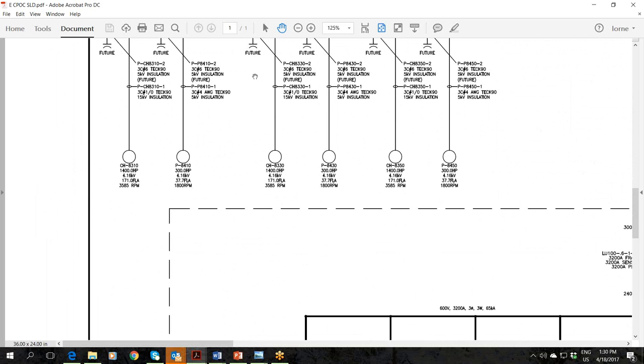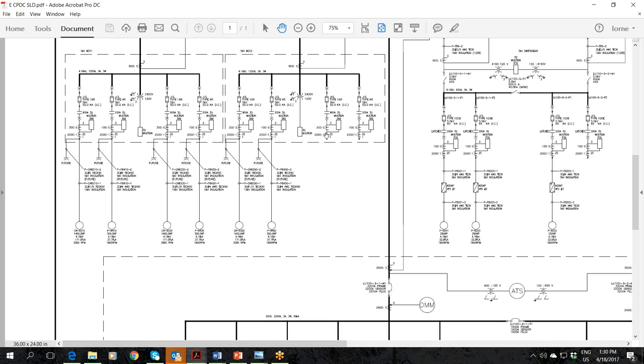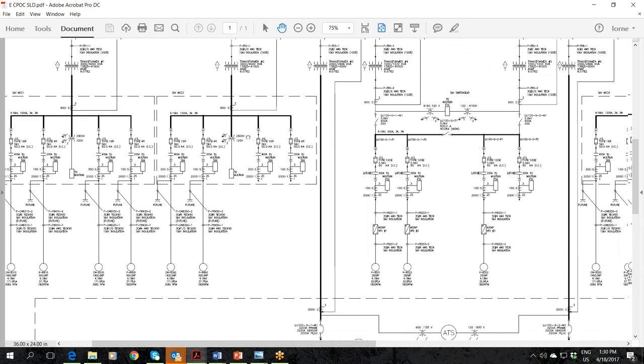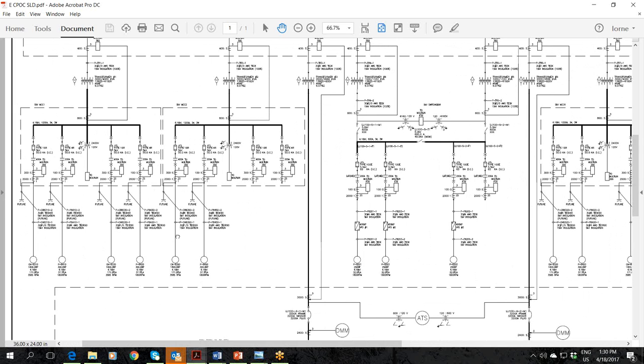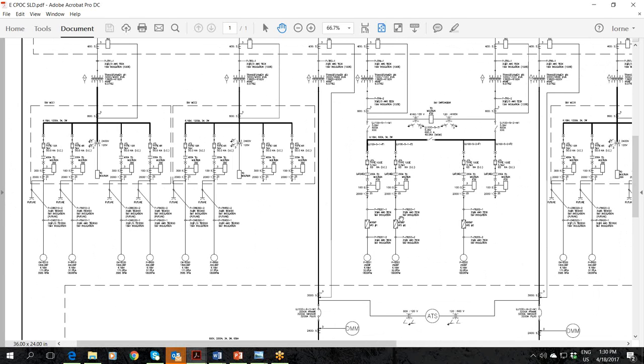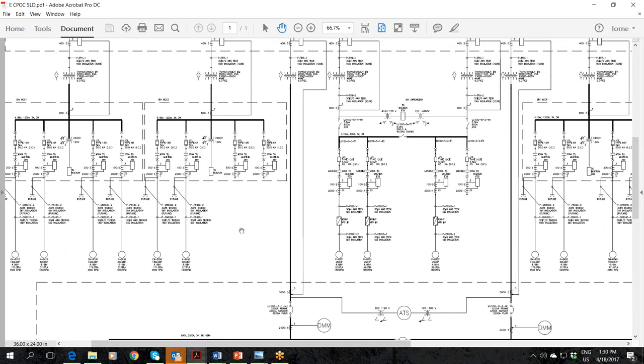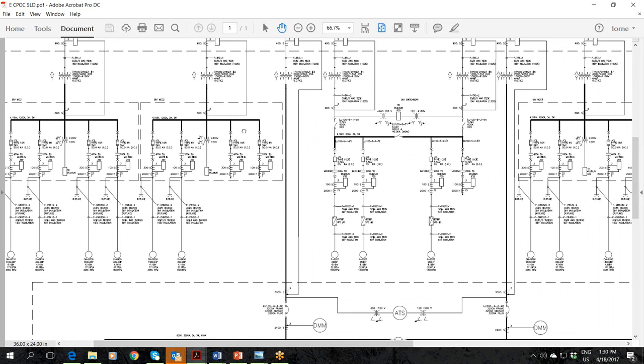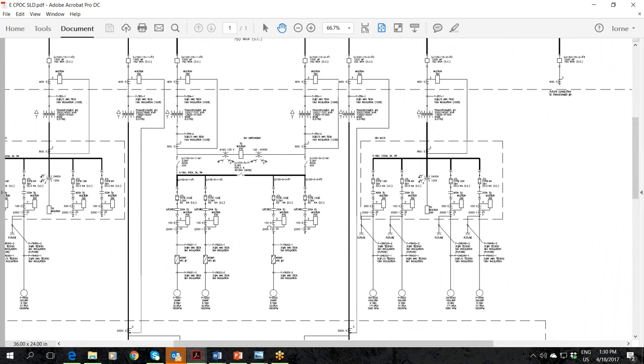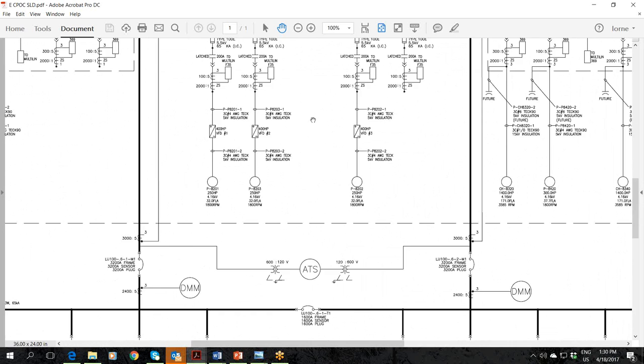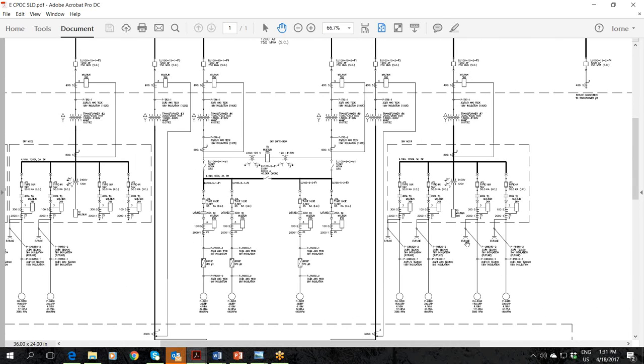So we've got 1400 horsepower, 300 horsepower. These are associated with our chillers that are associated with our chilled water system, which is of course used for cooling on the campus itself. So you don't see that main tie main arrangement here. Instead, we've basically got multiple chillers. I think there are 5 in the cooling plant on campus right now. It's expandable to 8 on the floor plan. So you don't need all the chillers all the time. Even at the peak, we could run, I think, without 1 or 2 of those chillers in service. So we didn't feel like we needed that level of redundancy in terms of a main tie main configuration. So we've done operational redundancy as opposed to electrical architecture redundancy. We did do a main tie main on these because these are primary pumps that are VFD driven for the chilled water plant.